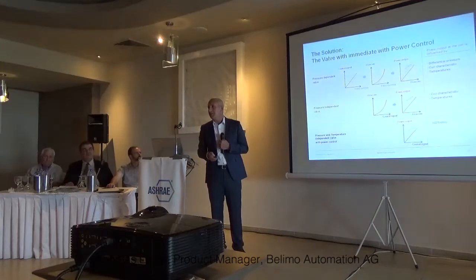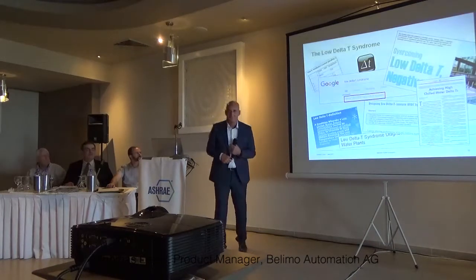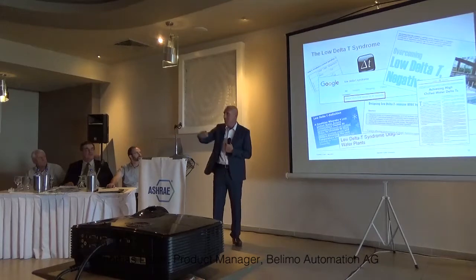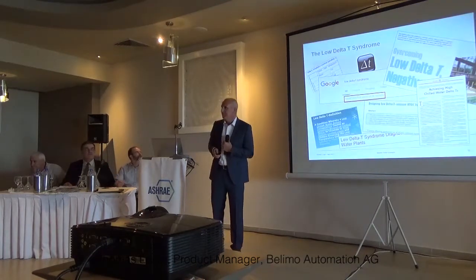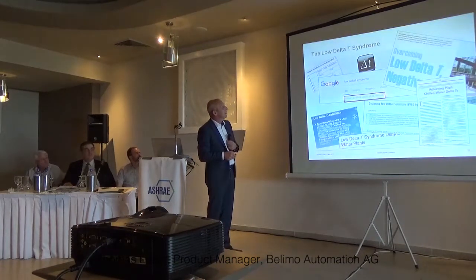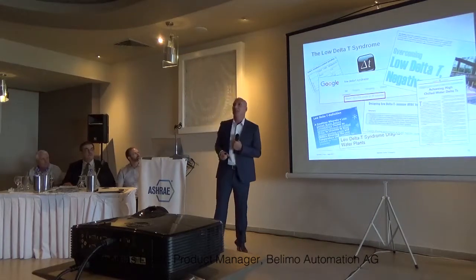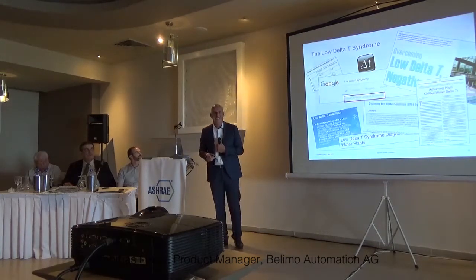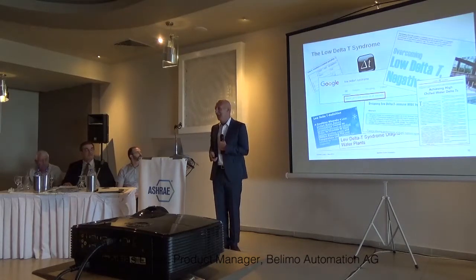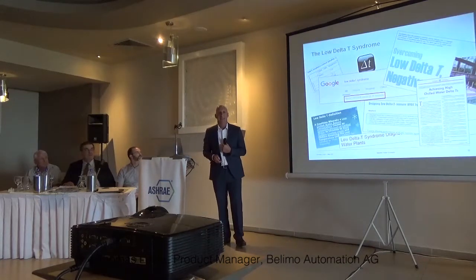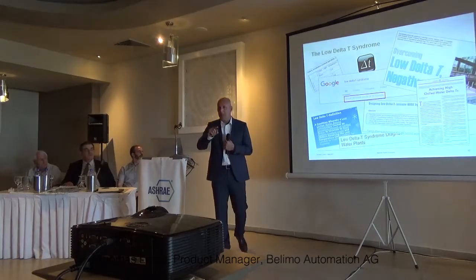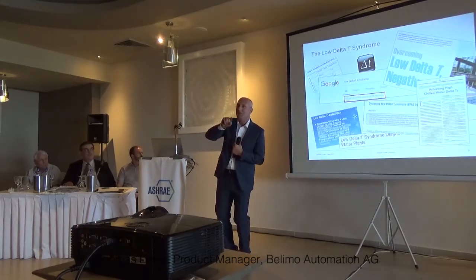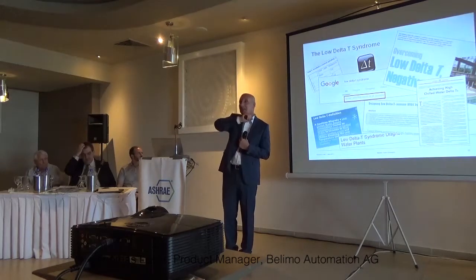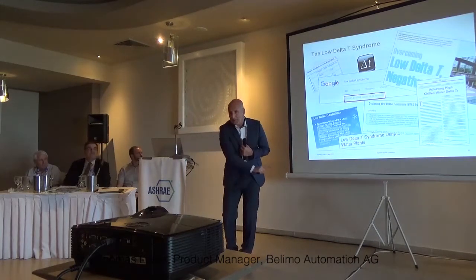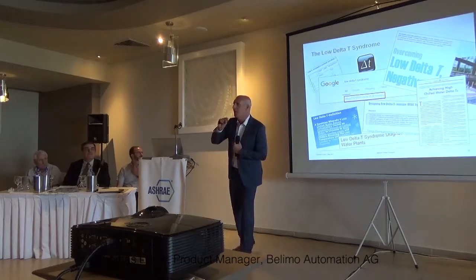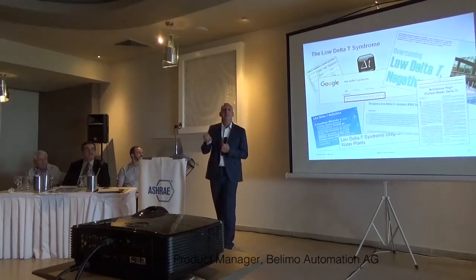What would be an application for this? Low delta T, as Jim addressed this morning, a big issue. I Googled and I found in half of a second 1.5 million articles mentioned there. So it is a big thing in our industry. Low delta T actually means the differential temperature, the difference between the supply temperature and the return temperature, is lower than expected. And this leads to a lot of problems.